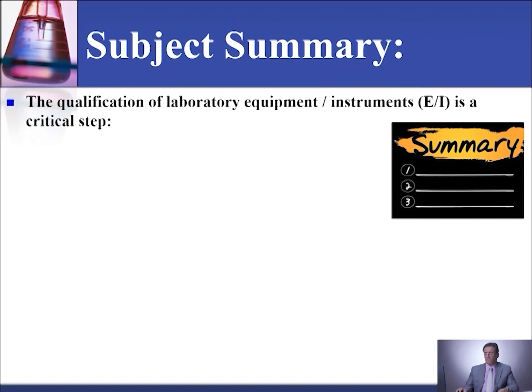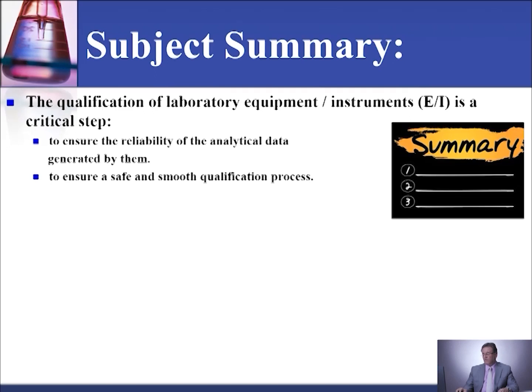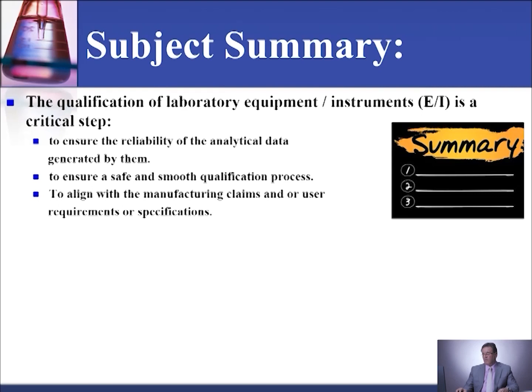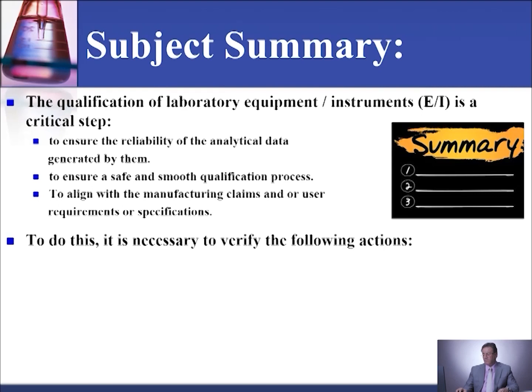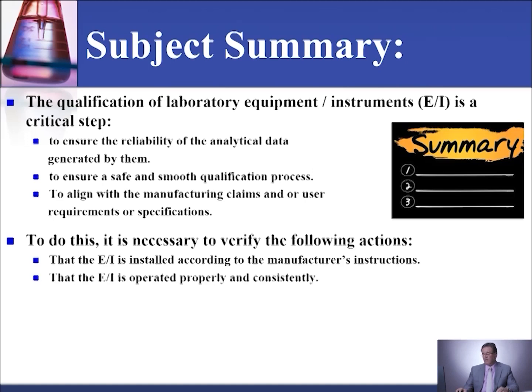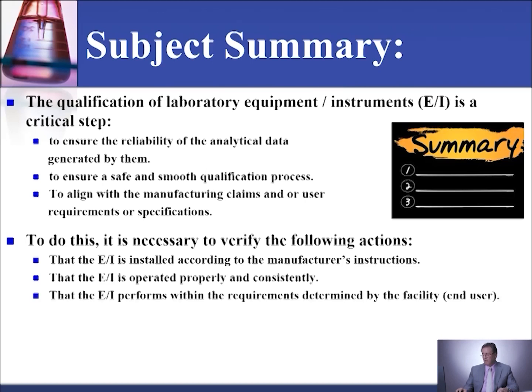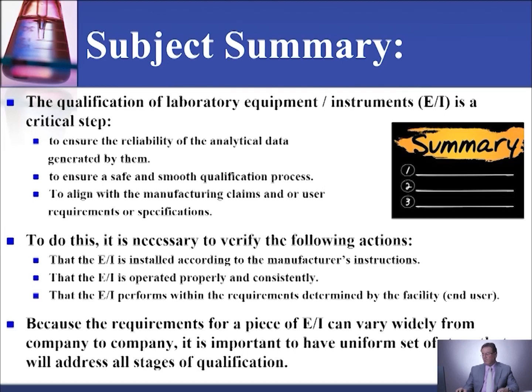Subject summary: the qualification of laboratory equipment and instruments is a critical step to ensure the reliability of the analytical data generated by them, to ensure a safe and smooth qualification process, and to align with the manufacturer's claim and/or user requirement or specification. To do this, it is necessary to verify the following: that the equipment or instrument is installed according to the manufacturer's instructions, that it is operating properly, and that it performs within the requirement determined by the facility, which is the end user, the laboratory, because the requirement for a piece of equipment can vary widely from company to company.